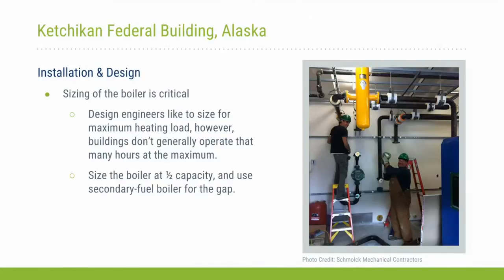In hindsight, if I had control, I would have sized this boiler at about half the capacity that it is right now, and that would have definitely impacted the operation and economics of this project. I am aware of other sites nearby in Ketchikan that have biomass boilers. They are grossly oversized and they're having operational issues as well. Next slide, please.